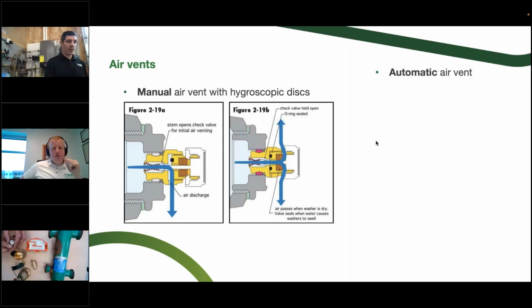Okay. Yeah, and the other thing to think about too is you mentioned heat exchangers. The fact is that pretty much every boiler on the market is going to come with some type of an air removal device on the top of it. They want to try to keep those boilers full of water, obviously not air. And not only that, the boiler is going to be one of the best places to actually remove air, because it's going to be one of the hottest points in the system, and that's when air is less soluble in your water or your fluid, so it's just an ideal place to actually get rid of air.